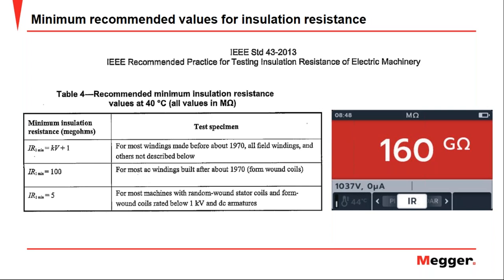So we have three categories here. The first, the winding made before 1970. For those motors, the minimum insulation resistance value is given by the mathematical expression that you can see in the table: kV plus 1. You have to go to the nameplate voltage, convert it to kV, and put it into the formula, and you have the minimum value for the insulation resistance for that motor.